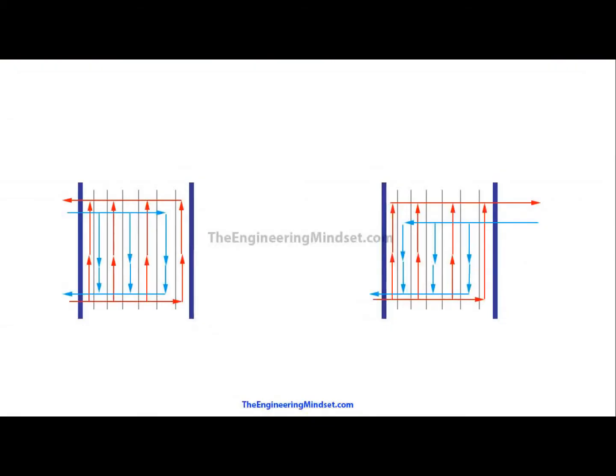Now there are a couple of ways the plate heat exchanger can be piped up. This is the most common version, and the one we're going to be looking at today, where the inlets and outlets are all on the front plate, so the fluids enter, flow through their channels, and make their way back to the front plate. The other version is where one of the fluids enters through the front plate, passes through, and exits through the back plate, while the other fluid enters there as well.